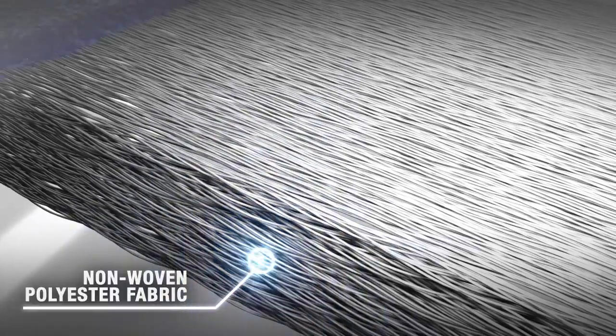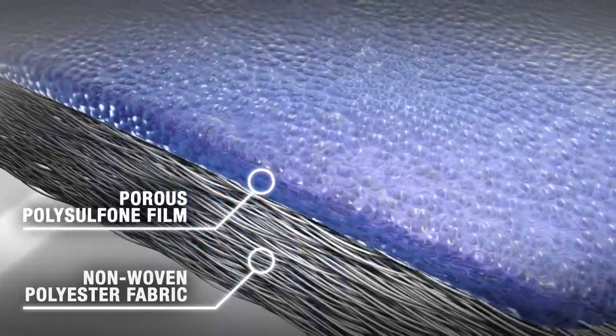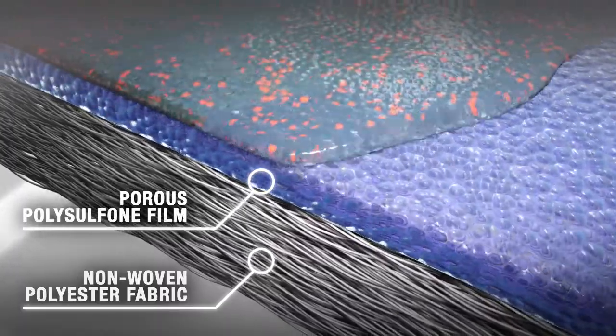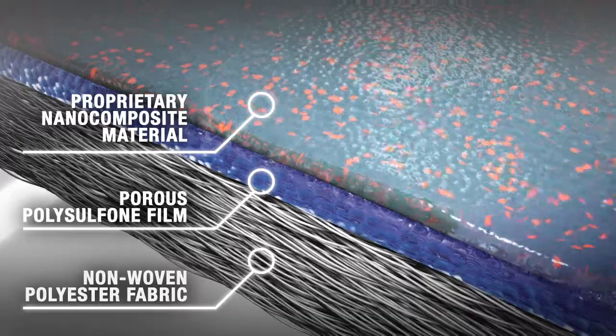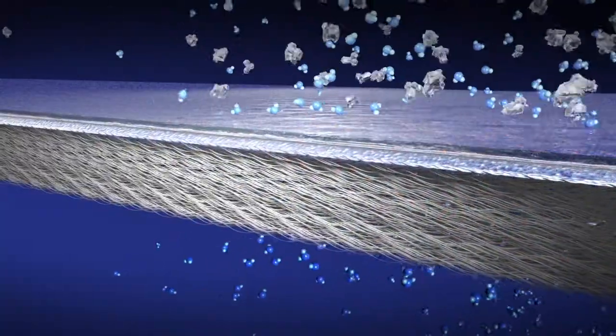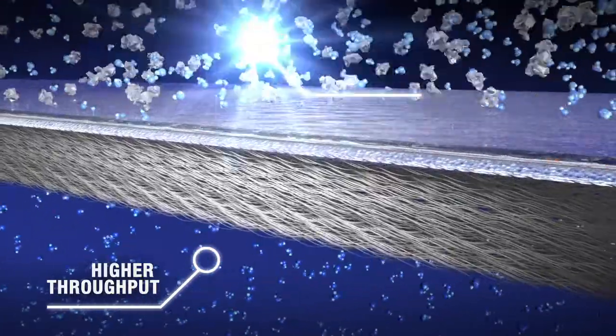Nano H2O's patent-pending technology encapsulates benign nanoparticles within the thin-film polyamide layer. Beginning with a non-woven polyester fabric, a layer of porous polysulfone film is cast, followed by a layer of Nano H2O's proprietary nanocomposite material. This exclusive process increases membrane permeability by 50 to 100% over conventional membranes, while matching best-in-class salt rejection.